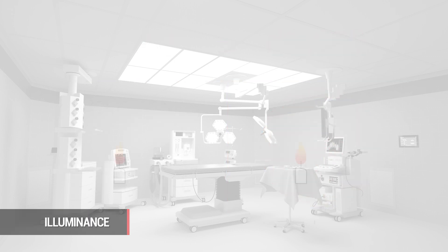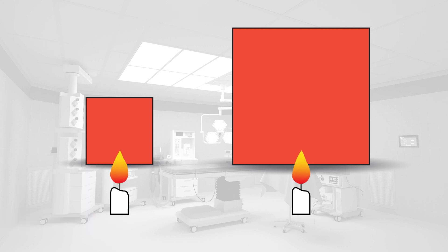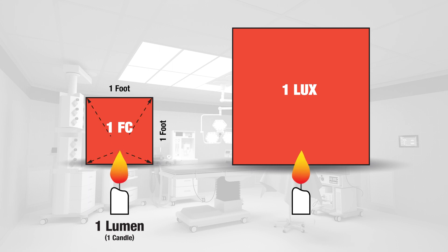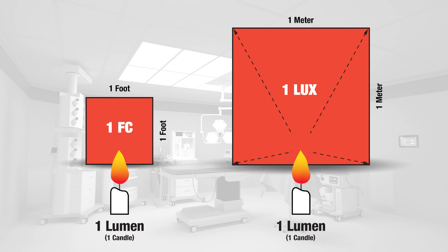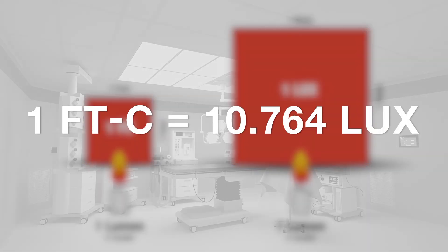Illuminance describes the quantity of light that arrives at a particular surface, like an operating table or workstation. This is measured in foot candles or lux. A foot candle is one lumen per square foot, while lux is one lumen per square meter. One foot candle is equivalent to 10.764 lux.